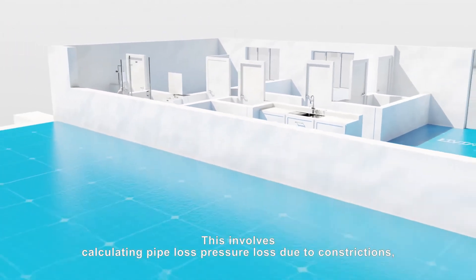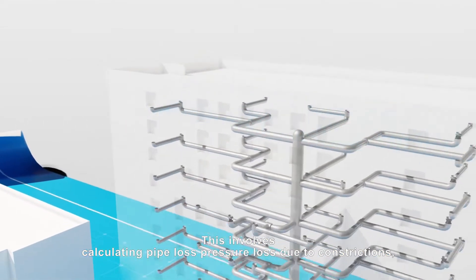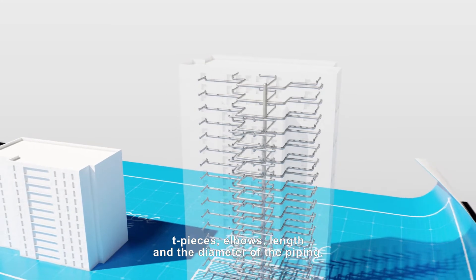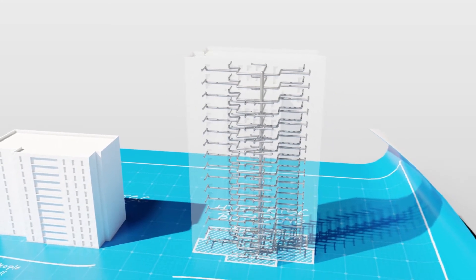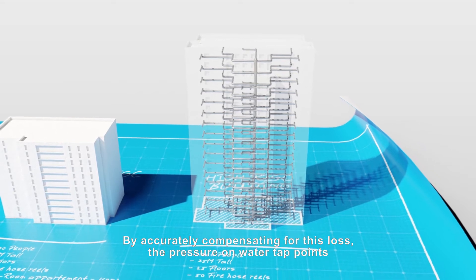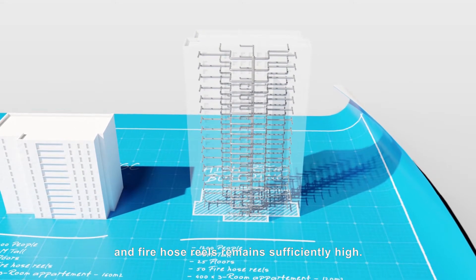This involves calculating pipe loss, pressure loss due to constrictions, T-pieces, elbows, length and the diameter of the piping. By accurately compensating for this loss, the pressure on water tap points and fire hose reels remains sufficiently high.